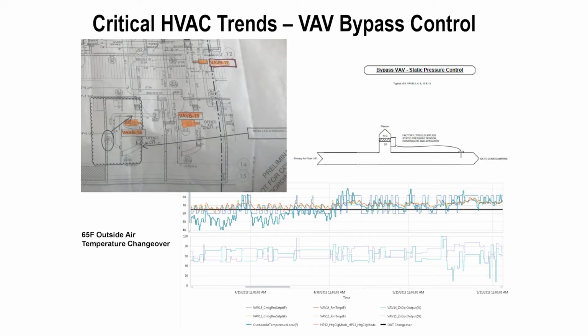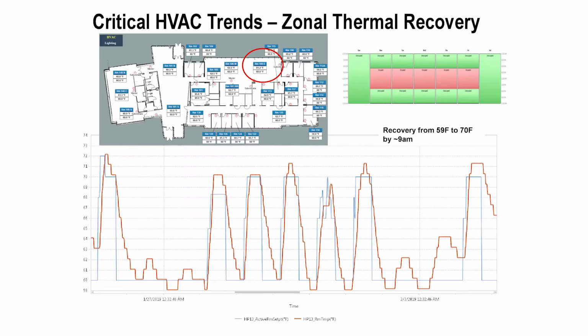So this becomes important when the outside air temperature is around 65, because I asked the controls vendor as we were going through functional testing, well, how do you know how to give priority to the spaces? I mean, should we do that based on outside air temperature? How are we going to do that? It wasn't totally flushed out in the design documents. So what we did was we used a 65-degree changeover temperature. Below 65, the priority is for heating. So if either zone needs heating, that's what the heat pump does. Above 65, cooling. And that seems to be working pretty well.